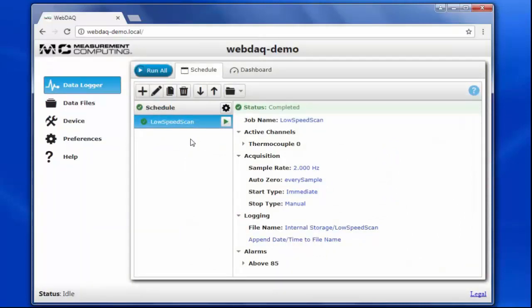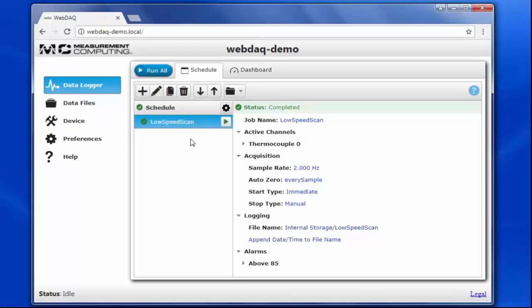Right now, when the temperature goes above 85 degrees, an alarm is triggered and logged to file. But let's say I want to switch to a different acquisition setup when the alarm condition is met. When the temperature exceeds 85 degrees Fahrenheit, I want to acquire data at a faster sample rate, then switch back to the lower sample rate once the temperature drops back below the threshold.